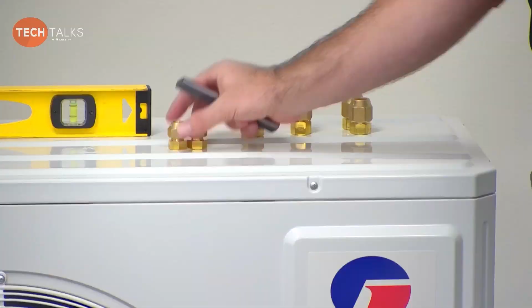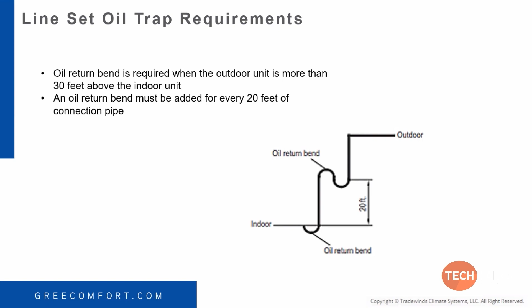If you're installing the outdoor unit above the indoor unit and you're further than 30 feet above, like if this building's roof is about 30 feet up, and you hang a high wall unit here, you'd need to put an oil bend in the pipe. You have to look at your max pipe length when doing that lift. There's a max lift and a max pipe length, and if you're over 30 feet, add an oil bend for every 20 feet of connection pipe. Generally you won't have a model that goes far enough to need two oil bends, since you'd be over your max lift or max pipe length.